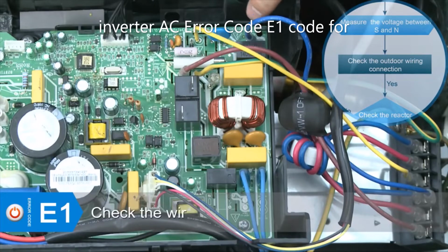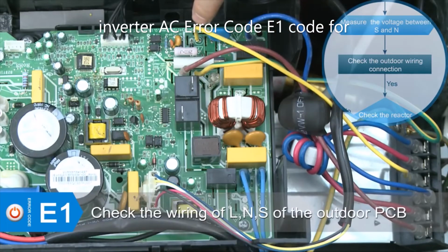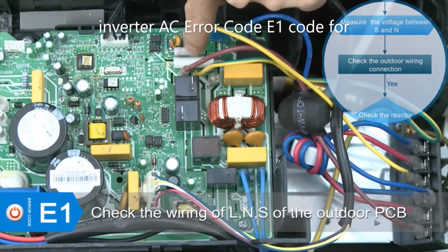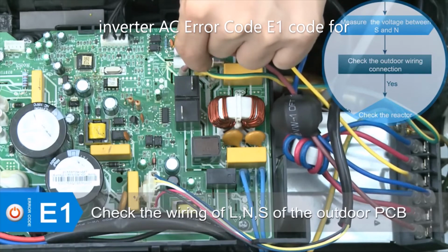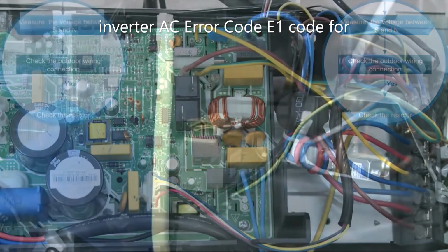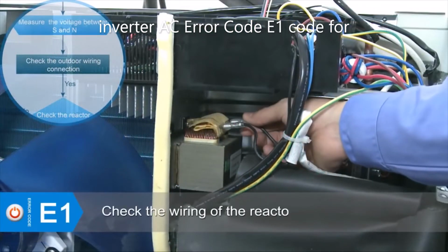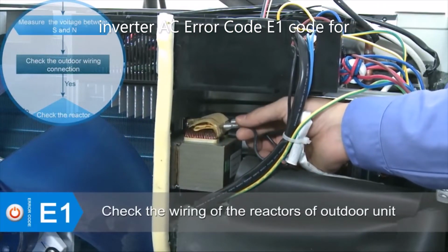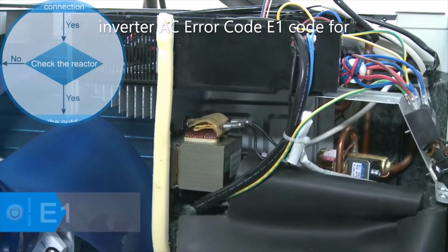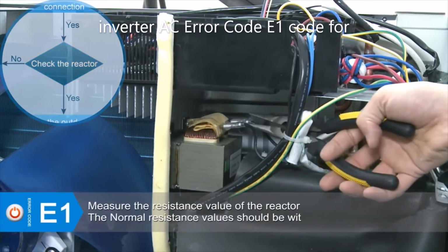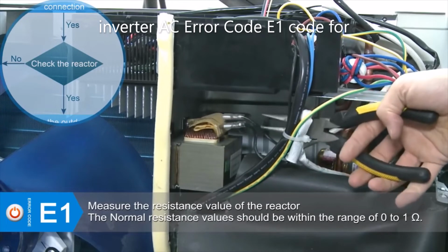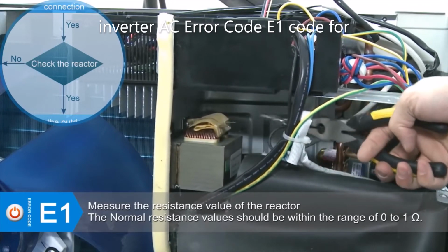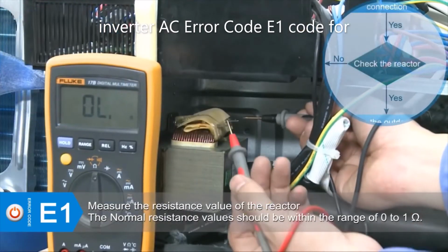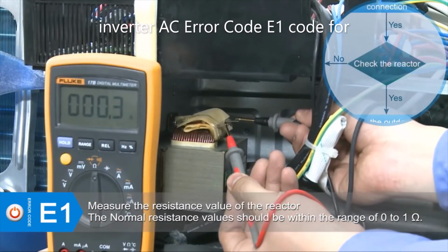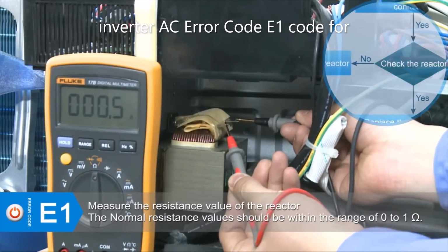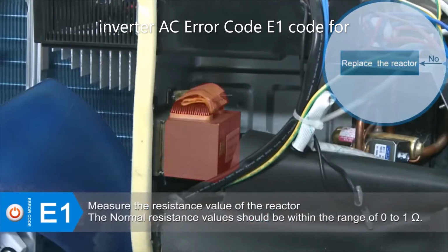Check the wiring of L, N and S of the outdoor PCB. Check if the wiring of the electric reactors of the outdoor unit is well connected. Measure the resistance value of the reactor. The normal resistance value should be within the range of 0 to 1 ohm. If not, replace the reactor.